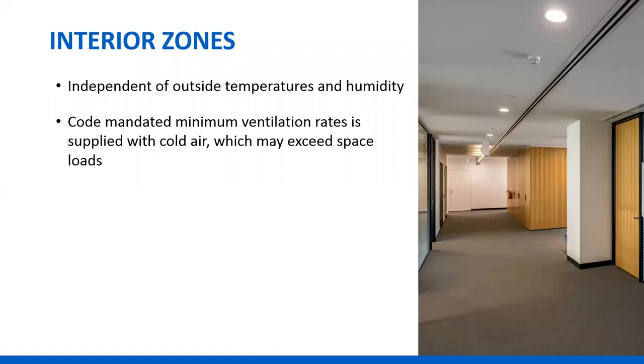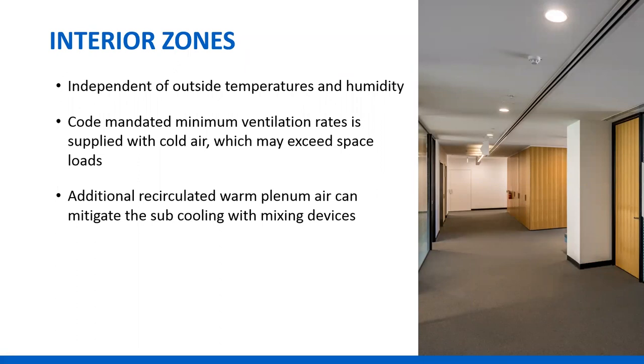Both ventilation and humidity control often require cold air. With the low loads we're seeing in offices today, we find cases where maintaining humidity and ventilation rates causes the space to become sub-cooled — we spent some time talking about that in the last talk. If we can take some warm plenum air and mix it into the interior zone, we can offset some of that sub-cooling.